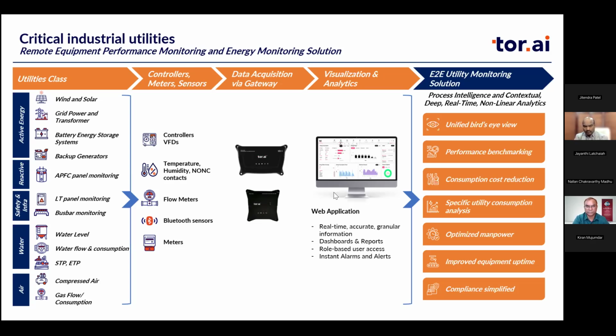That could be because of weaker or loose joints, or surface corrosion, or the load itself drawing a higher current than the rated current of the load. So these are the three reasons. The system should be able to acquire the data of these busbar temperatures and calculate, based on the flow of the current, the rise in temperature. It should be able to calculate the digital thermography on a daily basis.